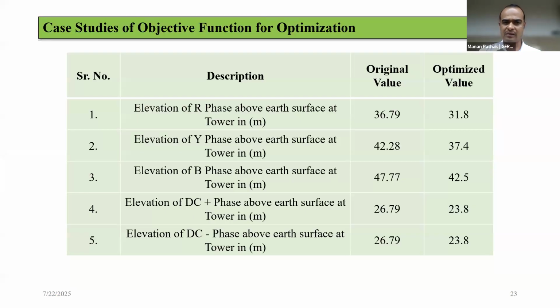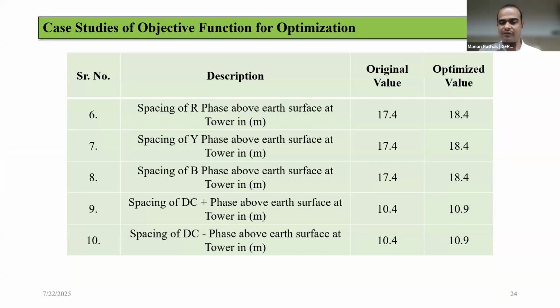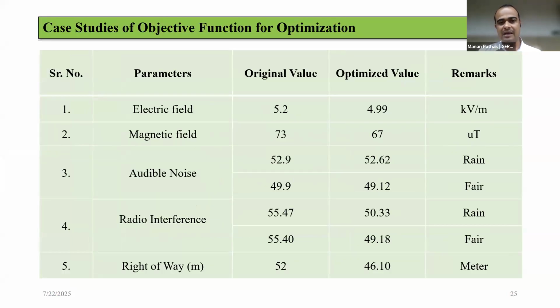These are some representations where we have changed the position from original to optimized value. According to the positions of R, Y, B, the DC positive conductor and the DC negative conductor, we can incorporate the spacing and verify the optimized results. And the main four parameters that we were supposed to discuss should be within range. Electric field we achieved 4.9, magnetic field 67, audible noise and radio interference again within the range of 49 to 50.33, and right of way as far as the double circuit is concerned is 52, and as per our results we achieved around 46.10 meters.